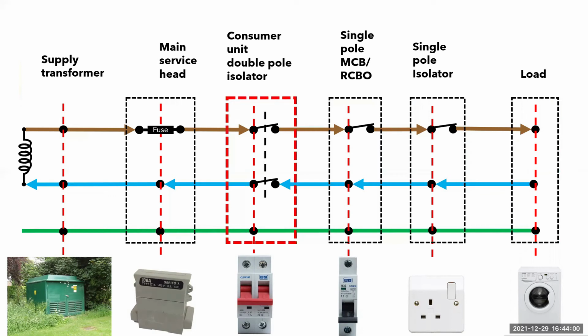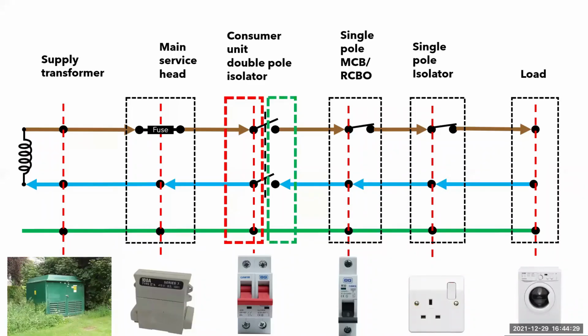This may not be an option, and you may not be able to isolate the boards in the assessment at college, and particularly it's currently not an option for the AM2. This means that your only option is to go through the safe isolation procedure by seeking permission, switching off the main switch, and locking this off before gaining entry, so that the supply side of the main switch is the only thing that is live, before proving the load side of the switch is dead.